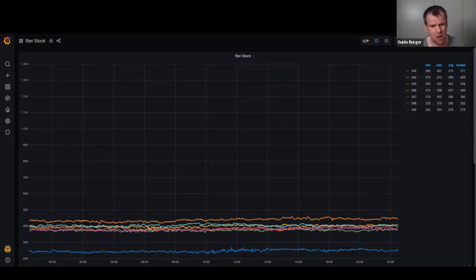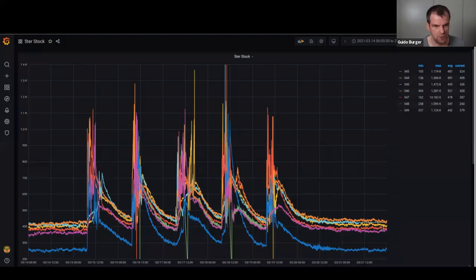We talked about how the outdoor air has something like 415, 420 ppm CO2. And this is the same wherever you are on the globe. There's only a little shift if you go higher or lower in altitude. So if you're on a mountain, you have a different CO2 level outside. But typically we are here on the ground on Earth, and there's typically the 420 something values. Now, as we know that, we can bring this blue sensor out into the fresh air and press our calibration button. That tells the sensor, what I'm seeing here is 415 ppm. So this curve will move after calibration into this crowd and be relevant for us for measurement.